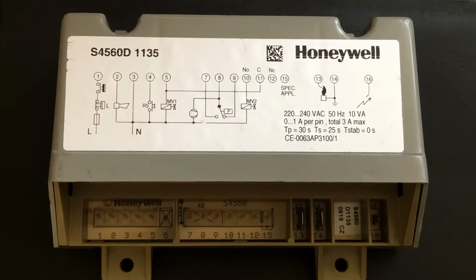Then it will continue the journey. After the differential pressure switch senses that everything is okay and the fan is running, the spark plug will be initiated, and if the spark plug is okay, then the first gas valve will be open. You can have a pilot flame to send a signal to the ionization probe. It will spark, the spark plug will be initiated, and then the first valve will be open. So what will be the first valve? The first valve is number 5.